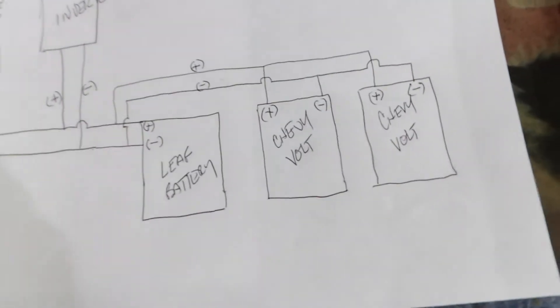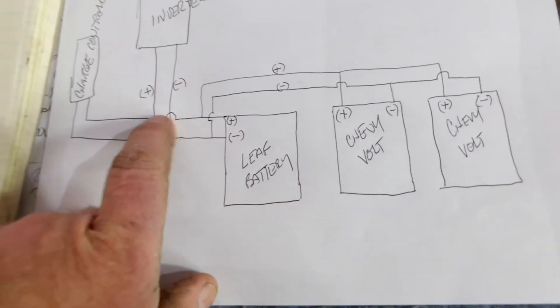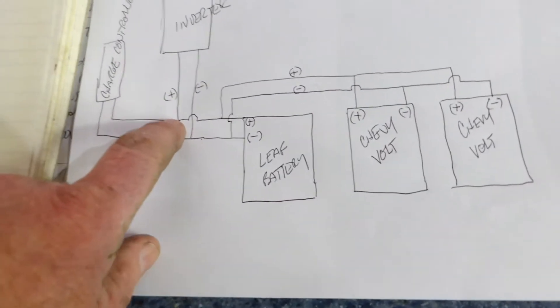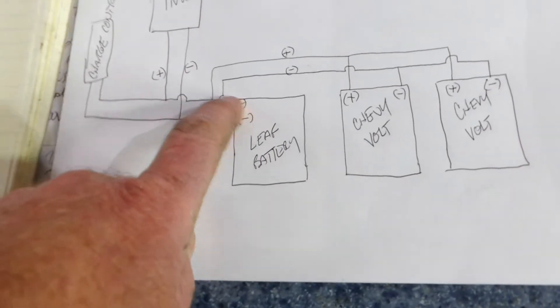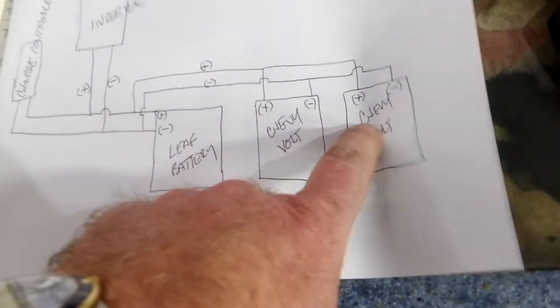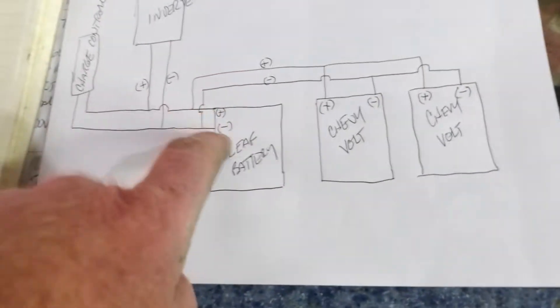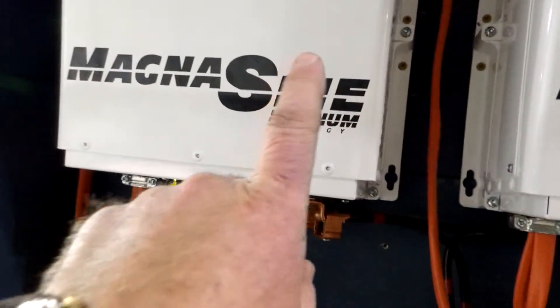They are in parallel, meaning the red positive wire that comes from the charge controller and goes to the inverter also goes to the positive on the Nissan Leaf pack and jumps over to the positive on the Chevy Volt, and likewise on the second Chevy Volt, and same for the negatives. To illustrate that, the charge controller wires come out - that's the positive - goes to a common lead and up to the Magnum inverter.